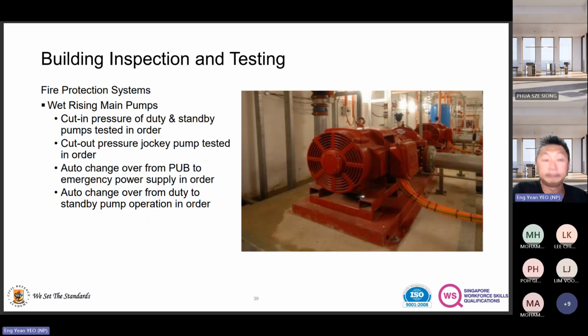So, think through again. The nameplate says jockey pump cut out at 180, meaning when the jockey pump comes in, for example the cut in is 170, you draw down to 170, the jockey pump cuts in. Then the pressure goes up to 180, and it cuts off. When this is stated in the nameplate, usually in red, cut out pressure for the jockey pump at 180, then it will stop automatically. If the gauge doesn't move, it means the pressure in that pipe must be 180 psi. That is the pressure in the system when it's in resting mode.